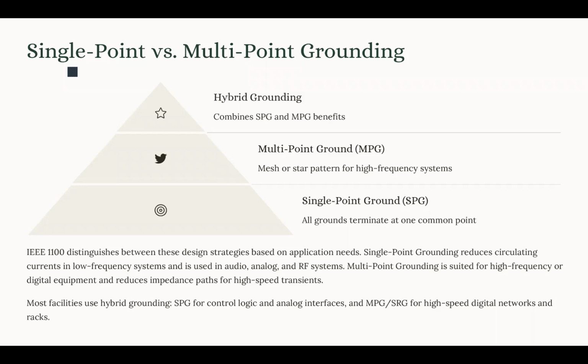This distinction has a reason, and it's because different types of systems have different grounding needs. IEEE 1100 specifies single point and multi-point grounding, depending on the operating frequency and the equipment sensitivity. Single point grounding means that all the ground terminates at a single common point. There is only one bonding point between the equipment chassis and the building ground system. Normally we use that in low frequency, high sensitivity analog devices like radio recording studios, medical imaging, or low frequency RF systems.